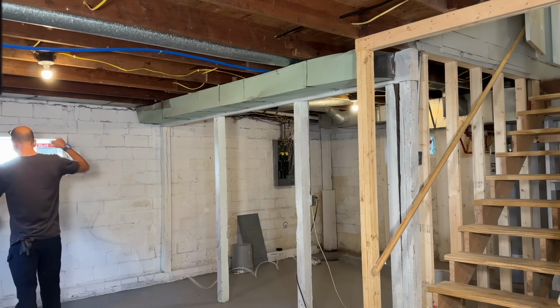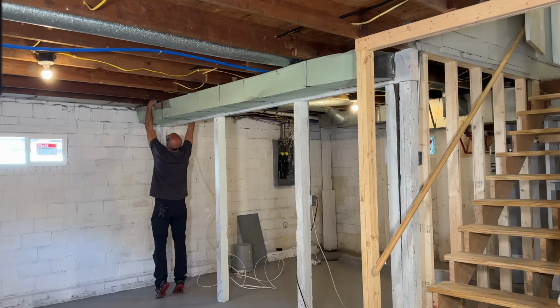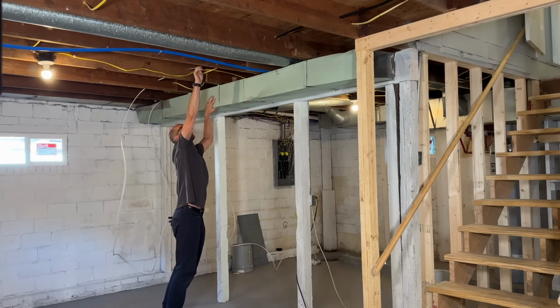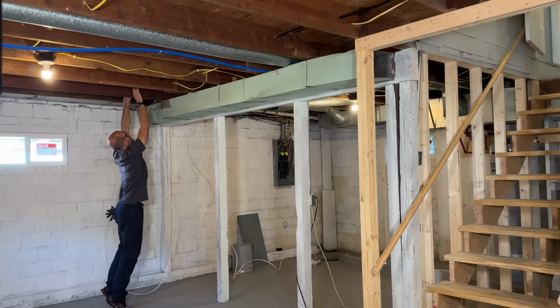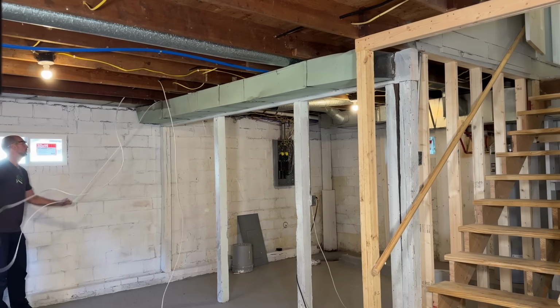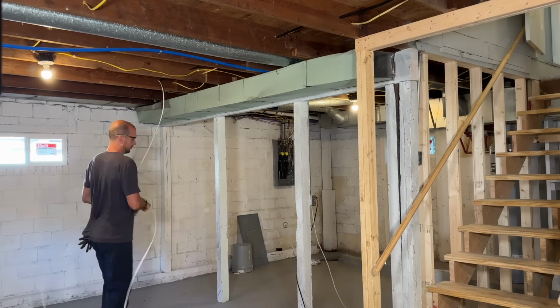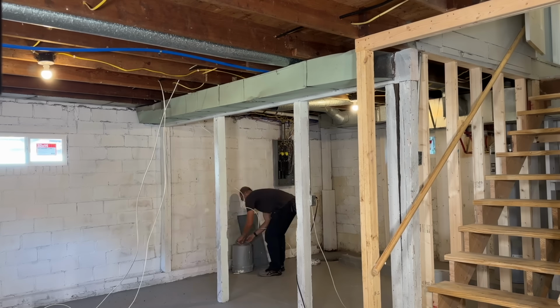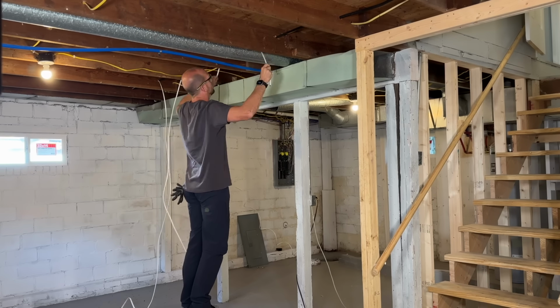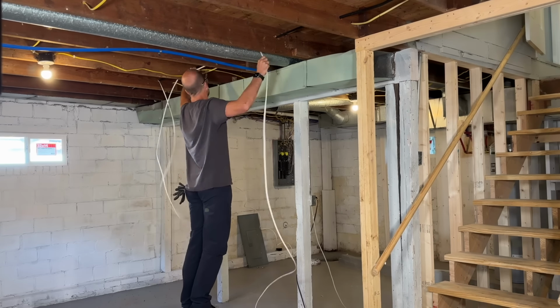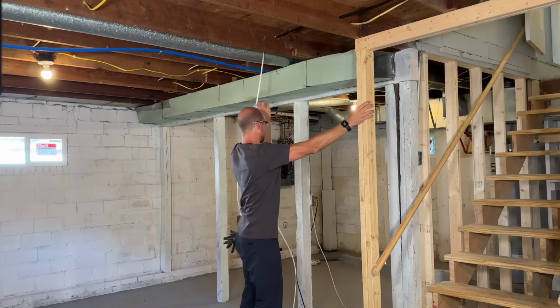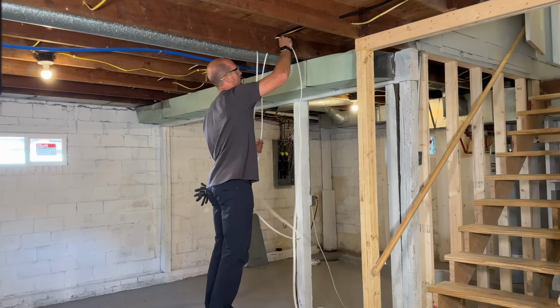Now we'll need to run another 240 volt circuit, and this is going to be powering the indoor unit, predominantly just the air handler and the circuit board. So this is only 15 amp, and as such, I'm running 14-2 Romex, 14 gauge, 2 conductor Romex, which will give us the circuit that we need to power that indoor unit.